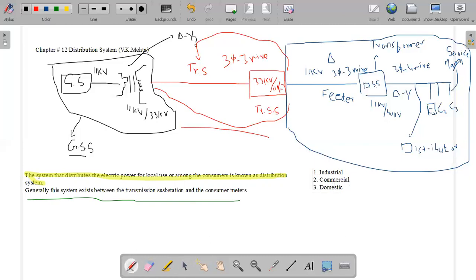For the industrial consumer, the voltage delivered is 11 kV, which they further step down according to their need. The commercial consumer normally requires a three-phase 400 volt supply. The domestic consumer depends - it may use single phase 220 volts, or a three-phase connection of 400 volts. Due to these different voltage requirements, we need to distribute these voltages among the consumers - this is the main reason for the distribution system.